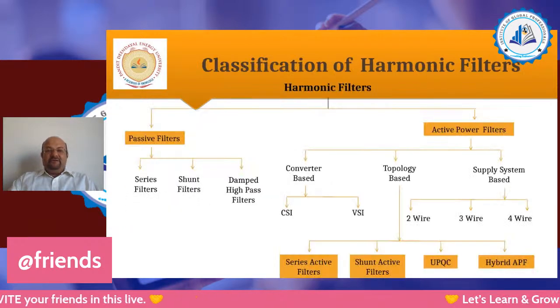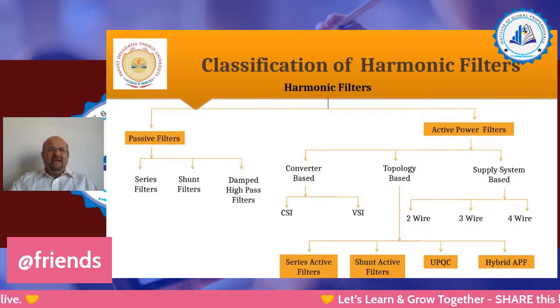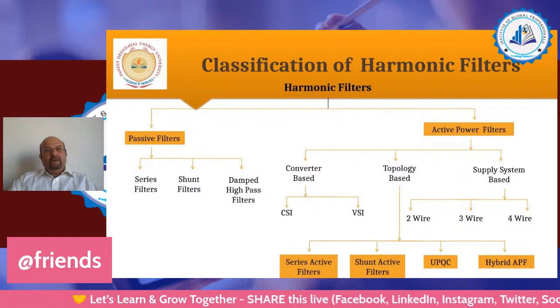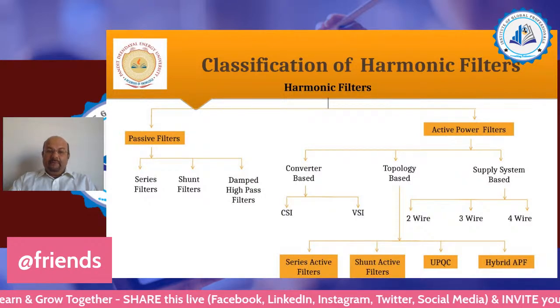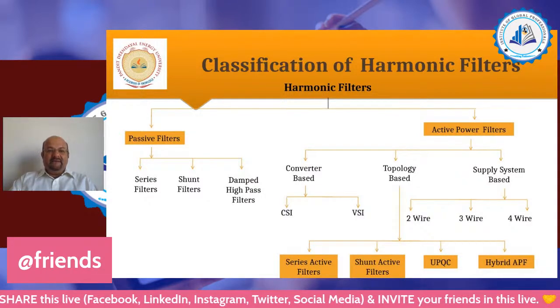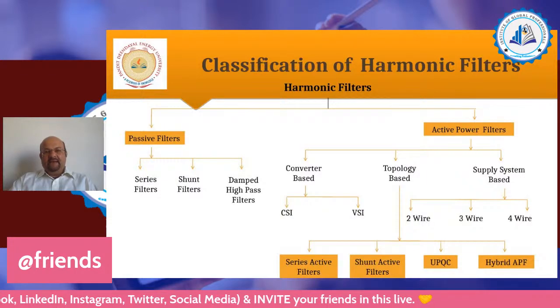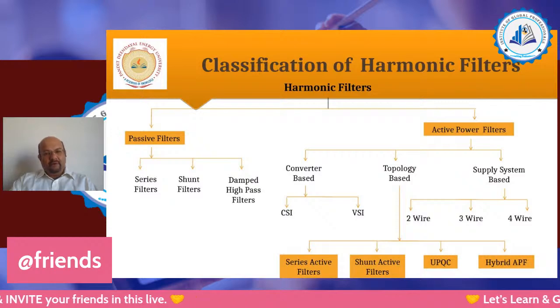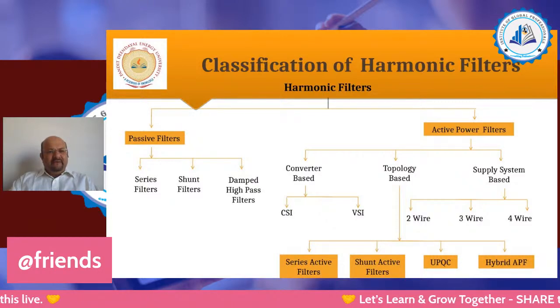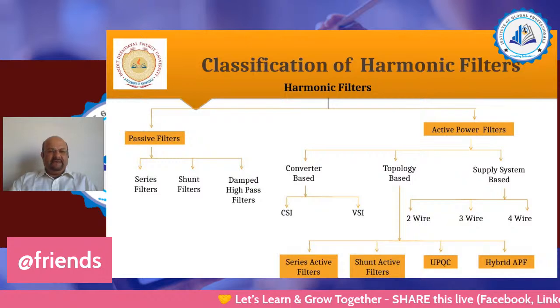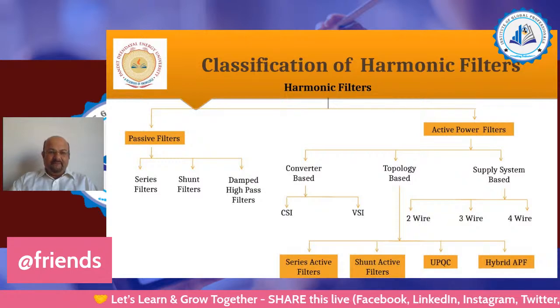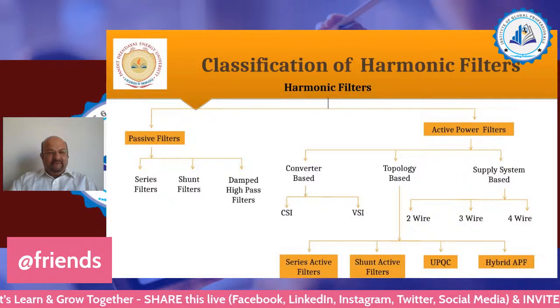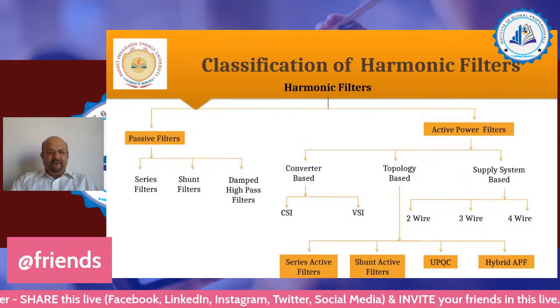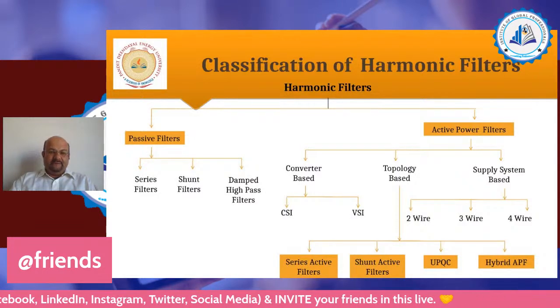Now next is classification of harmonic filters. As we have seen, the biggest villain in our power system is harmonics. To mitigate harmonics, there are two approaches. One is the conventional one, which is passive filters, and the other is the latest state-of-the-art advanced technology, active power filters. A passive filter, as the name suggests, uses resistance, inductance, and capacitor in a particular fashion. There are three topologies: series filters, shunt filters, and damped high pass filters.